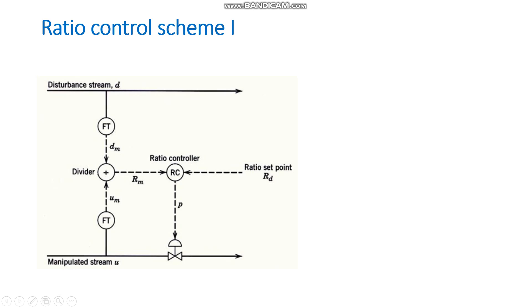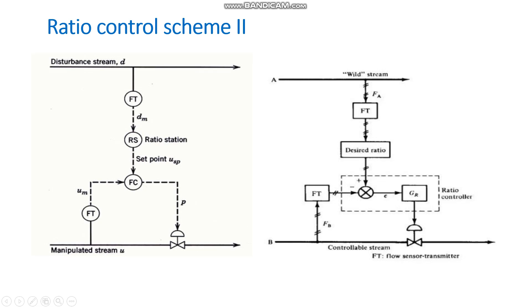The two flows are measured and sent to a divider, where their ratio is formed. This ratio is given to the ratio controller, which compares it with the ratio set point. The output of the ratio controller goes to the control valve, which increases or decreases the flow to maintain the desired ratio. This completes scheme one of ratio control.